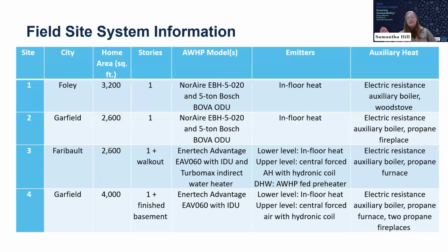At site 3, we cranked up the complexity and we had space heating, space cooling, and domestic hot water in a 2-story home. The basement had radiant in-floor heat. The upstairs had a centrally ducted propane furnace upgraded with a hydronic coil, which could provide cooling and heating. And then the air-to-water heat pump was set up with a domestic hot water preheating tank, which fed into a traditional electric resistance domestic hot water tank to preheat all the incoming water so that there was less domestic hot water load. And then our final site was very similar to site 3, but we skipped the domestic hot water. So it had floor heating, space cooling, and space heating through that hydronic coil with a backup propane furnace.